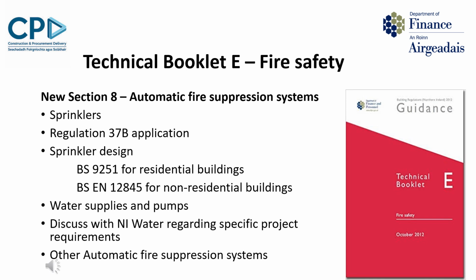In relation to new Regulation 37B, the guidance lists the prescriptive list of buildings the regulation applies to and clarifies the types of work when the regulation applies, i.e. it applies when a building is newly erected, when a building is formed after a material change of use, and to certain extensions and/or alterations to existing buildings, but only where 37B has been applied and the building is already provided with an automatic sprinkler system, and hence extending the system into the extended, altered bit of the building and recertifying the system makes sense.